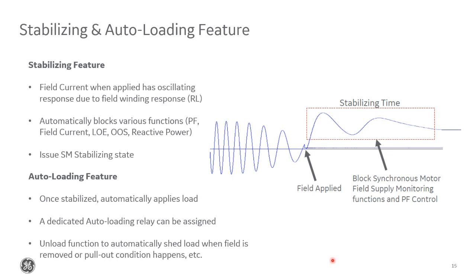Now, in terms of what the field current looks like during this process, you can see here that the motor is coming up to speed. The current is AC due to the induction from the stator. Right after we close in the DC supply here, there's a stabilizing time while the current levels off from AC to DC. During this time, there could be some unusual oscillations. So to prevent a relay misoperation during this time, we monitor this oscillatory period and we block the protection functions that look at the field current. At the point when the field current levels off, the relay registers that we're in normal synchronized running mode.